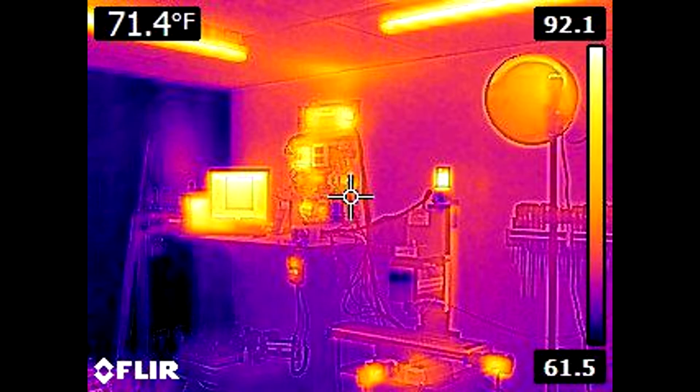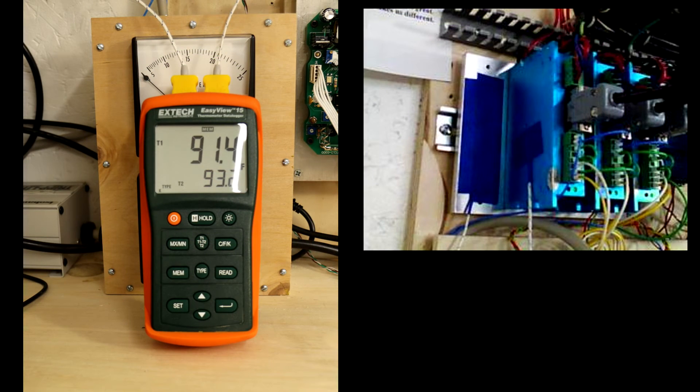For greater accuracy, direct measurements are preferred if possible. We'll use an Extech EA-15 temperature data logger to simultaneously monitor temperatures of the heat sink and drives during our tests. The K-type thermocouples are sandwiched between the measured surface and some tape.